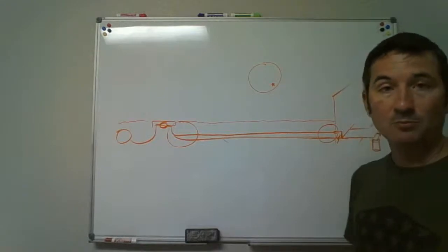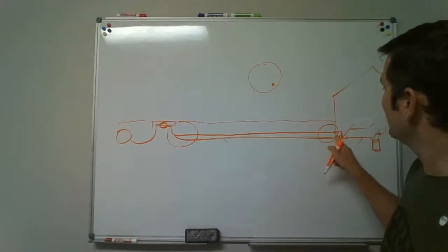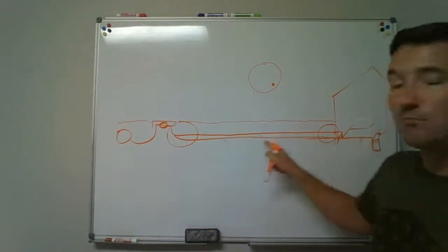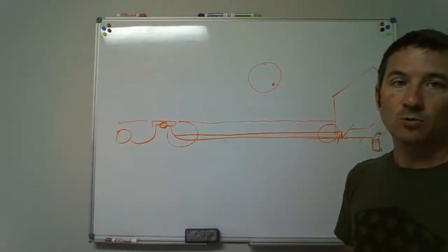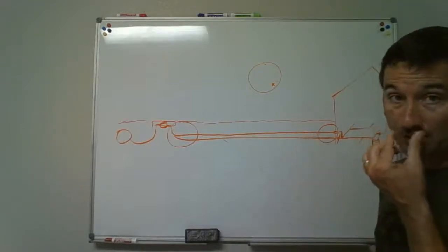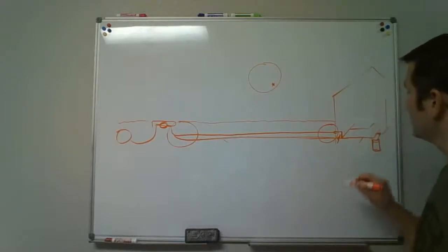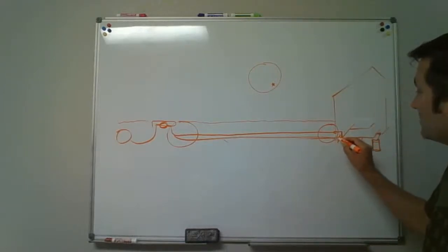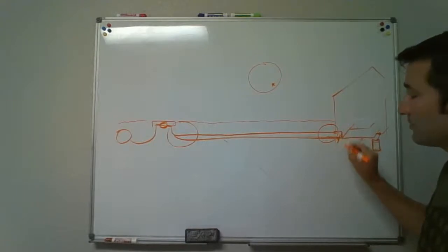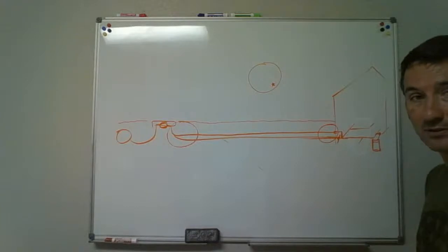But now the problem is we broke the ground. It's no longer running metal pipe out into the ground. We're running this plastic pipe out to the ground. So that does no good for grounding his electric panel. But I still left this piece of copper stubbed through the wall, the old line that did go out to the ground. I left that in the ground.